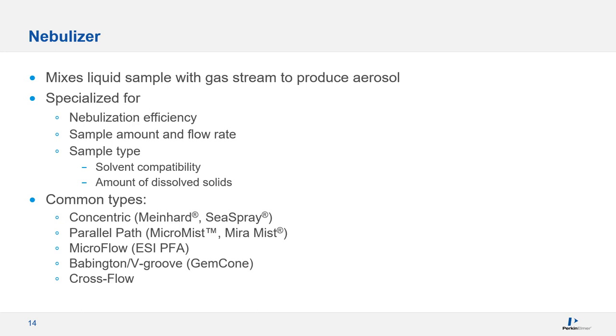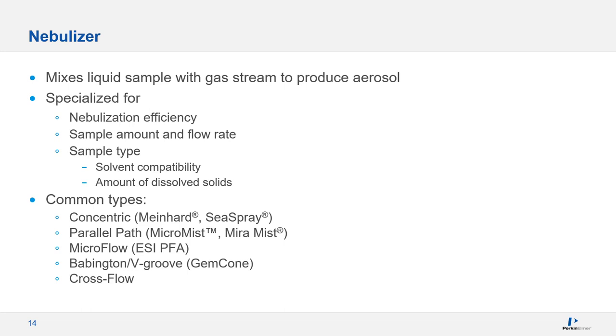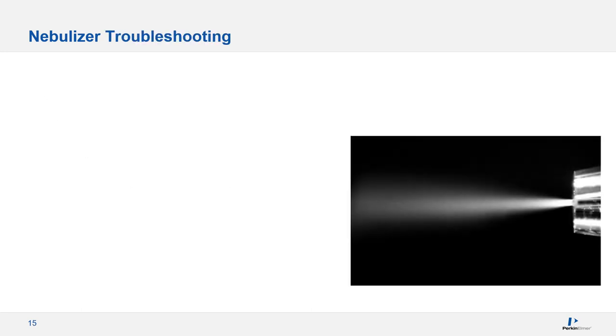Some commonly used nebulizer types are Concentric, where the sample capillary is fully inside the gas stream. Parallel path, where the sample stream and the gas stream run parallel to one another. Babington and v-groove, where the sample flows over the gas orifice. And then the cross flow, where sample and gas flows occur at right angles to one another. Because they allow for large diameter sample capillaries, the babington, v-groove, and cross flow nebulizers are harder to clog and work well for high dissolved solid samples.